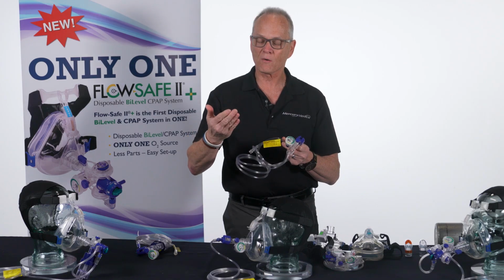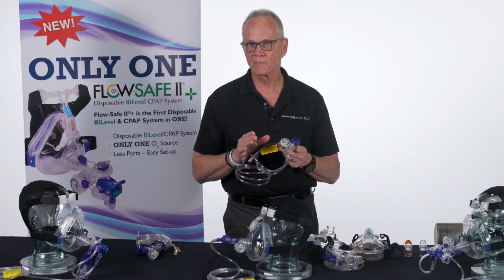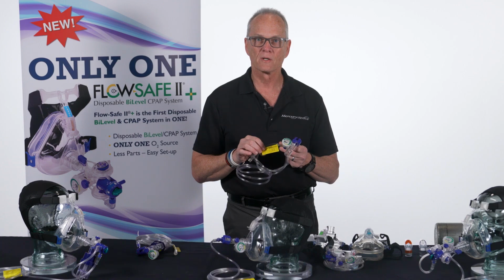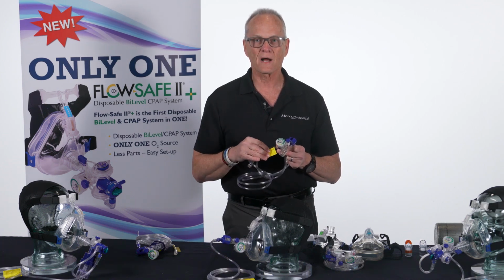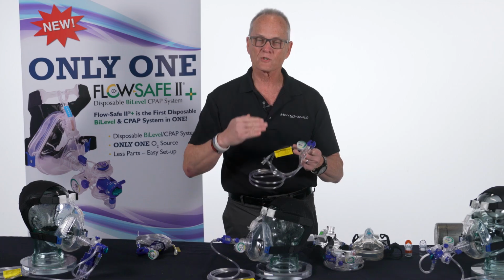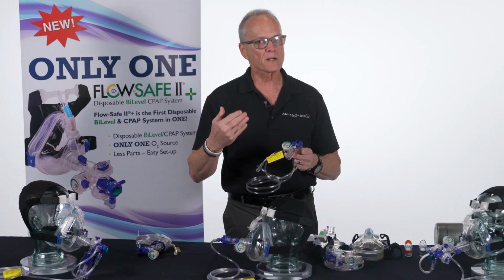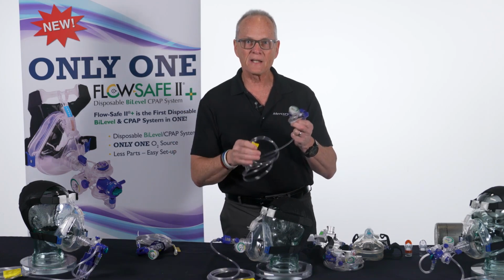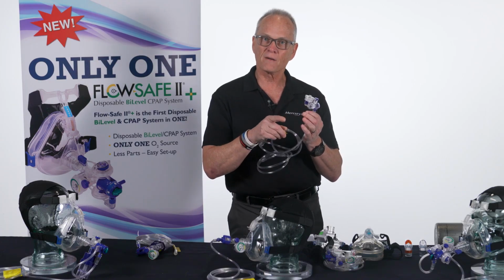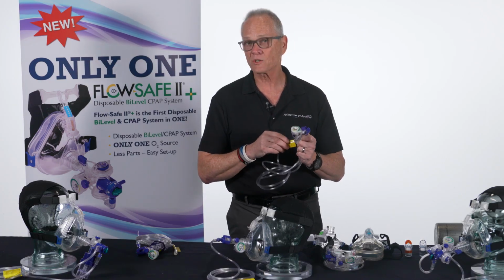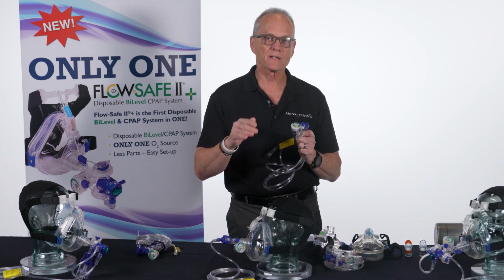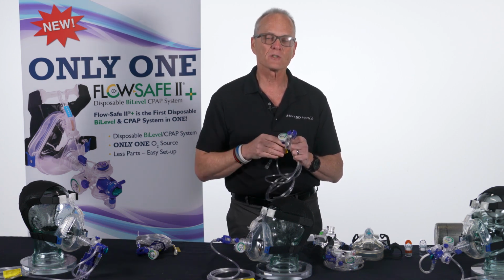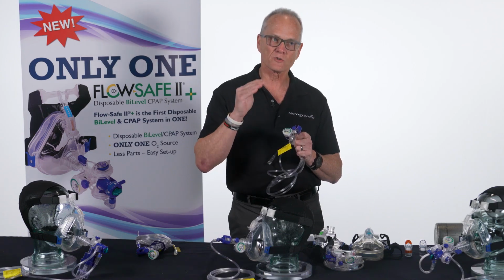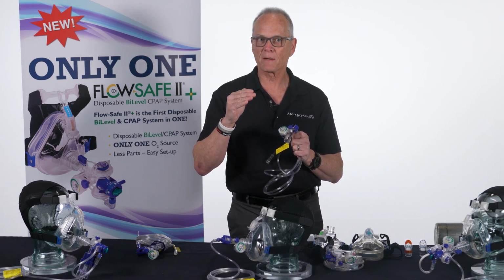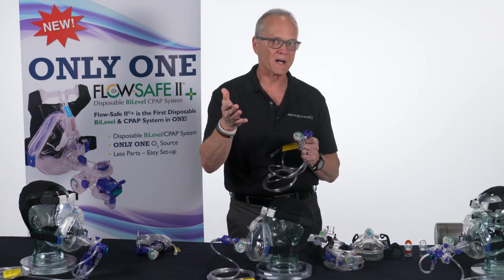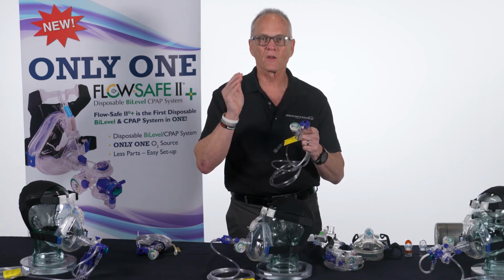So it's safe to start out with a FlowSafe 2 knowing that about 8 liters is going to give you 5 centimeters of water pressure. But once I get this on the patient's face, I may have to use more flow to actually get that. Now, those in the audience that may have just heard me say that 8 liters is going to give you 5 of CPAP, well, I can tell you 8 liters is not enough gas flow for the patient in respiratory distress. These patients are going to need gas flows probably at about 65 liters per minute of forward velocity. And now it's not volume, it's velocity.